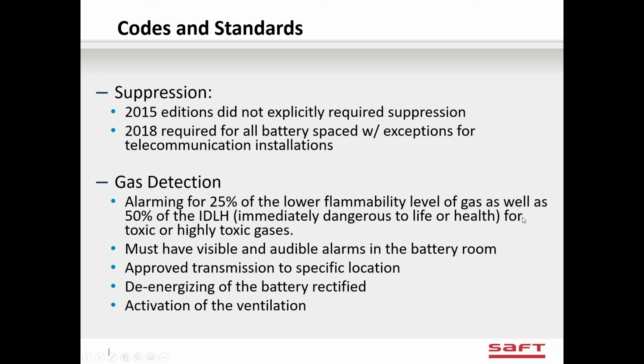This was the main problem with that explosion that happened in Surprise, Arizona with the energy storage container. The flammable gases that were vented from the batteries built up inside the container, and then when they opened the door, the gas air mixture got just right and exploded. I don't know if I have, there's a big report. I might not have all the details. You can read that report, but that is why the gas detection is supposed to activate the ventilation system to exhaust the gases.